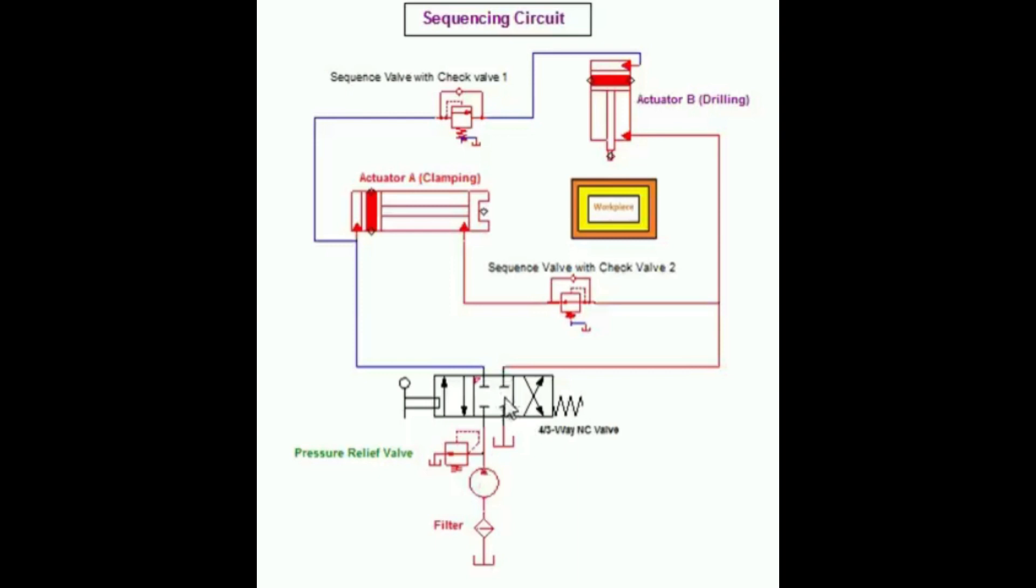In order for this circuit to function properly, the clamp cylinder must extend completely before the drilling cylinder begins to extend.